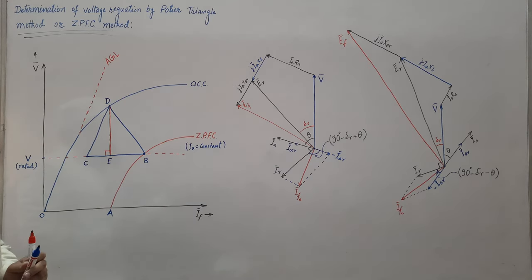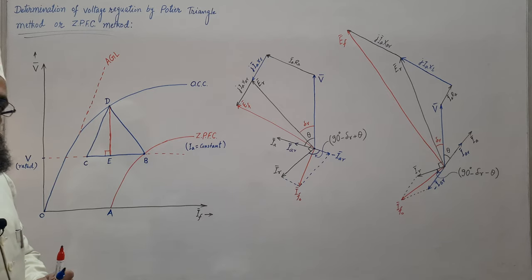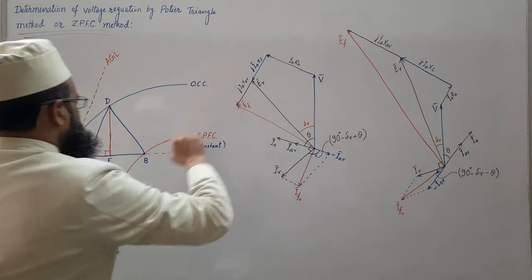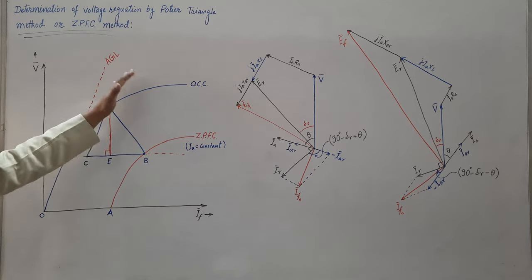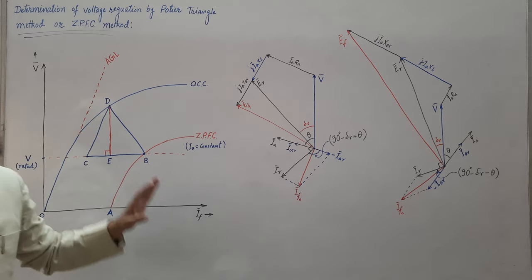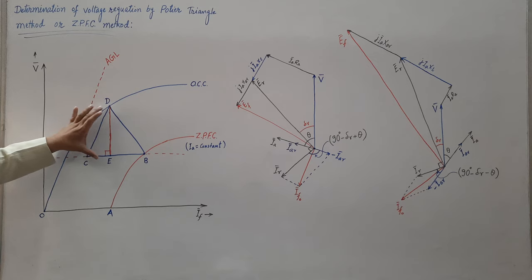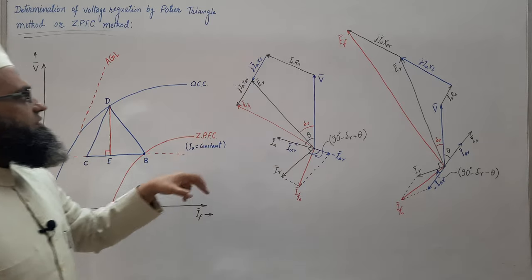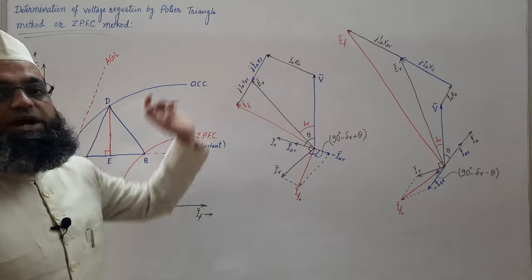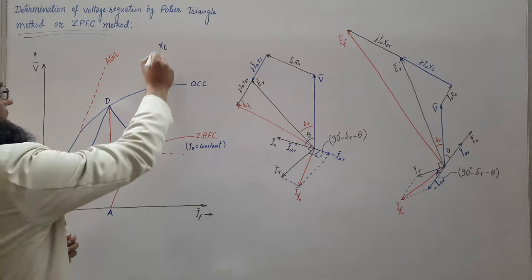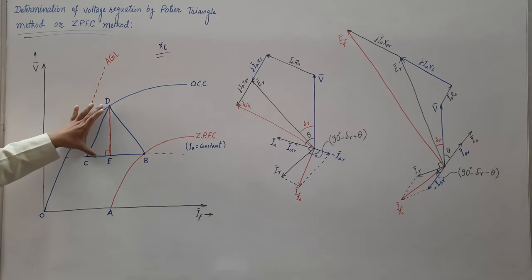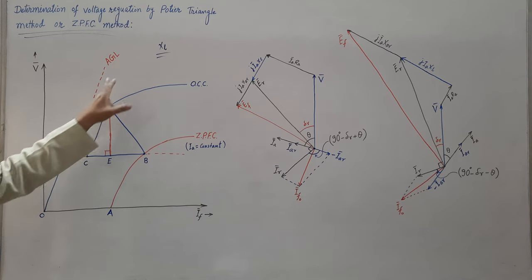CE represents the field current required to overcome the leakage reactance drop IAXL, and this side DE also gives the value of IAXL. Once this side is known, after performing the two tests and forming the triangle on graph paper, we can get the value of DE. This gives IAXL. Once IAXL is divided by the rated armature current, we get the value of XL.